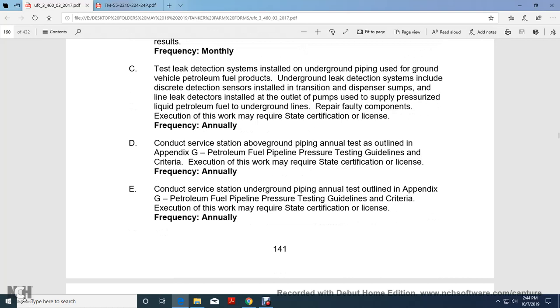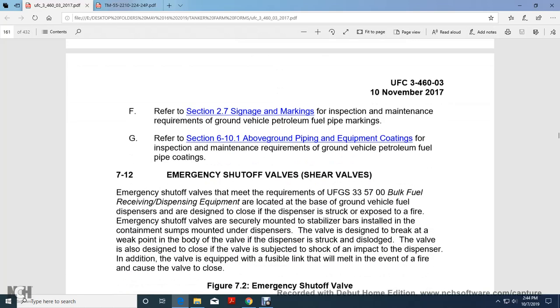Conduct service station aboveground piping annual tests as outlined in Appendix G of the petroleum fuel pipeline pressure testing guidelines and criteria. Execution of the work may require state certification or license annually. Conduct service station underground piping annual testing under Appendix G, petroleum fuel pipeline pressure testing guidelines and criteria. Execution of the work may require state certification and license annually. Refer to Section 2.7 for signage and marking, and to 6.10 for aboveground piping equipment coatings, for the inspection and maintenance requirements of ground vehicle petroleum fuel piping markings and coatings.